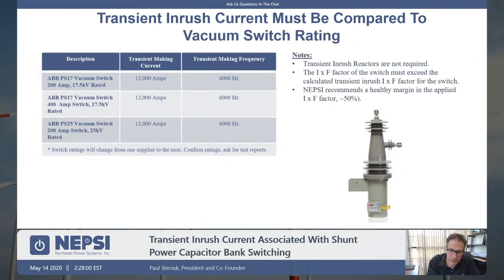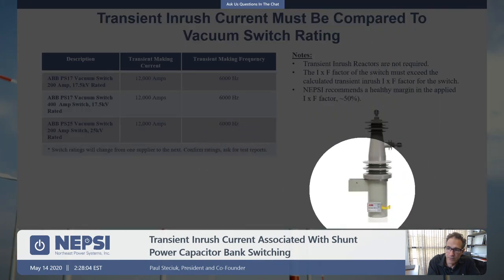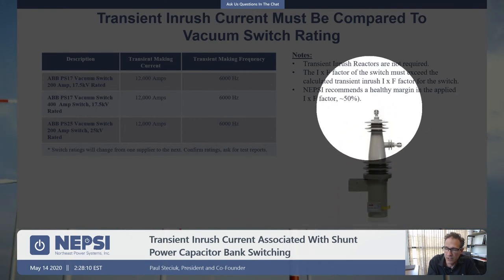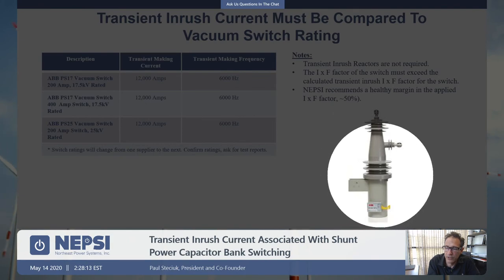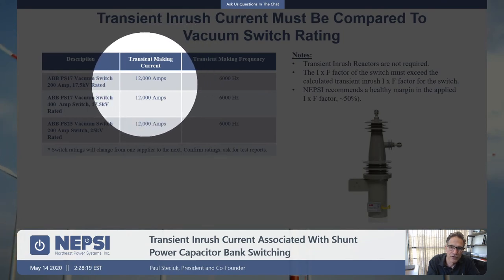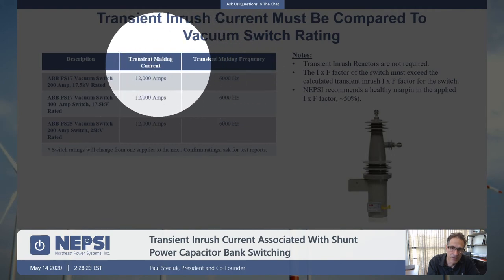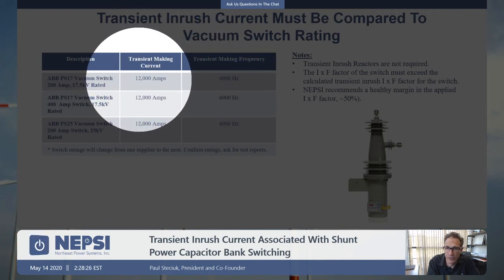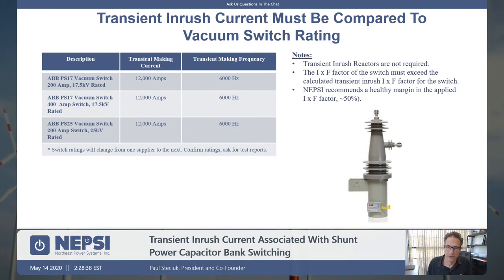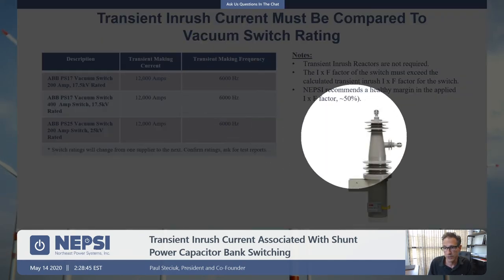The ABB PS17 and PS25 vacuum switches go up to 25 kV. They are single-phase, solenoid-operated devices rated at 200 or 400 amps. They publish a transient making current and frequency — for example, 12,000 amps at 6,000 Hz — giving an I×F factor. Calculate your cap bank's I×F based on installed inductance, compare against the switch rating, and target 50% or less. This is our recommendation.